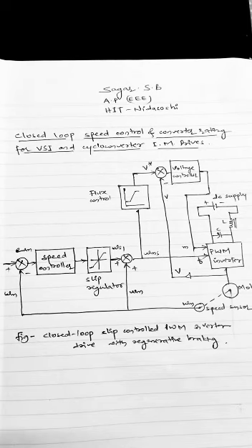The advantages of this drive include a faster response because the speed error is corrected at maximum available torque, and direct control of slip ensures stable operation under all operating conditions. Say we need to operate beyond the base speed, then it is required to increase the slip speed limit of the slip regulator linearly with the frequency until the breakdown value is reached.